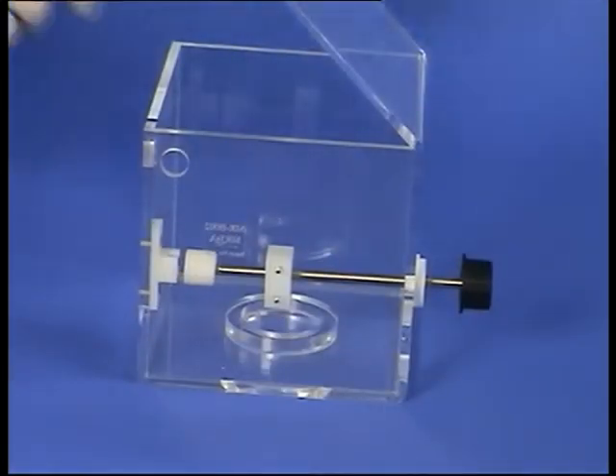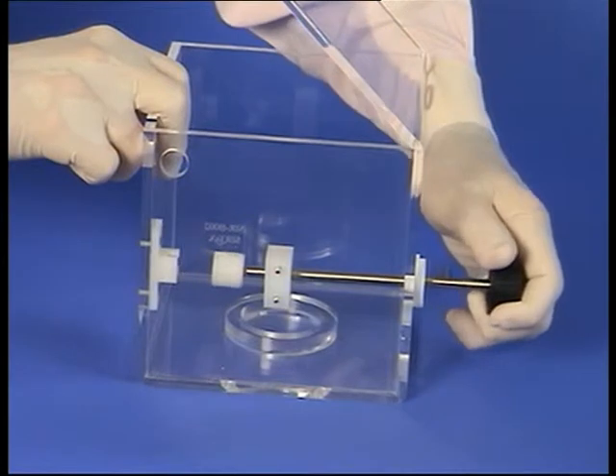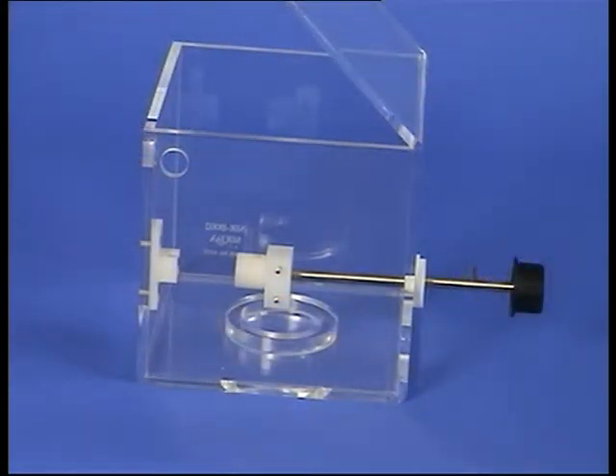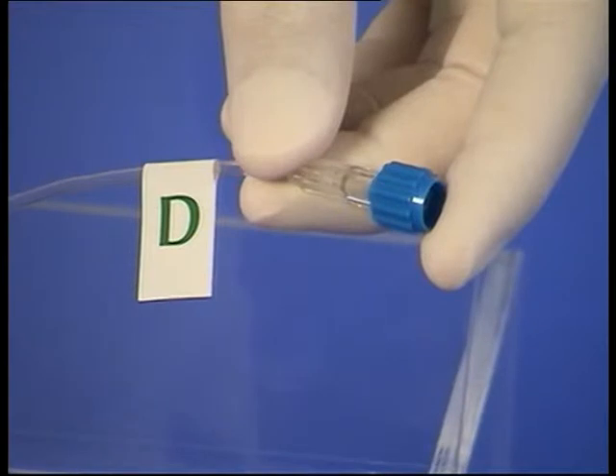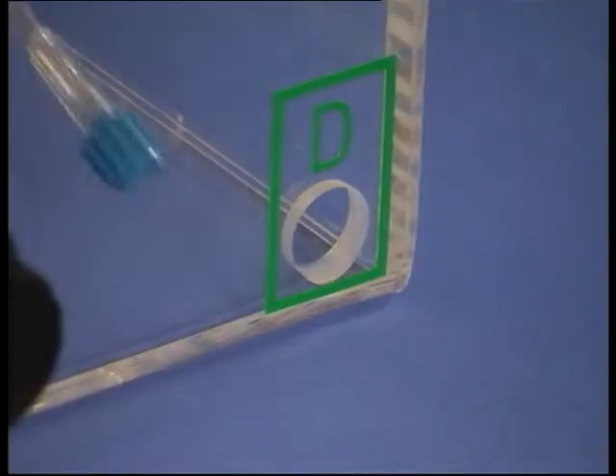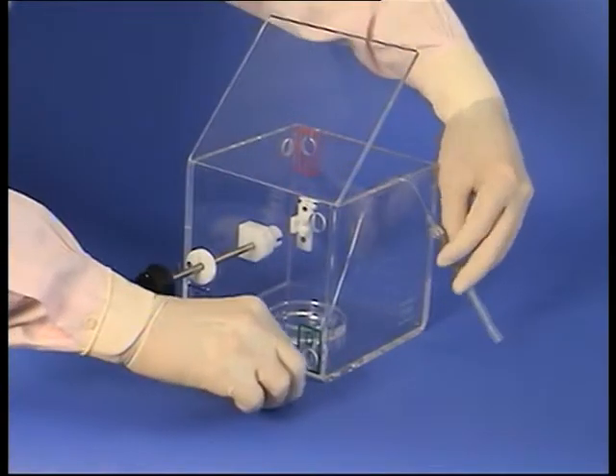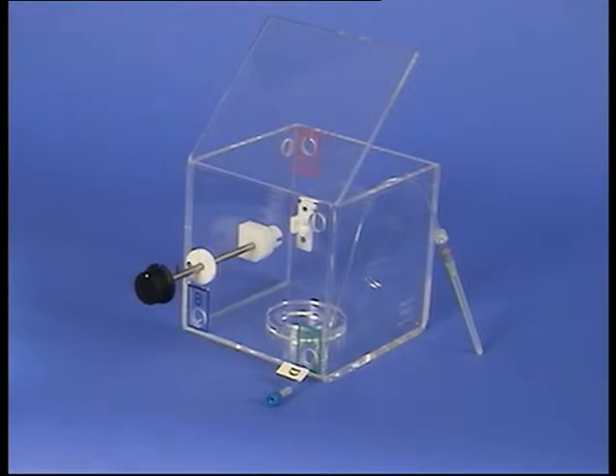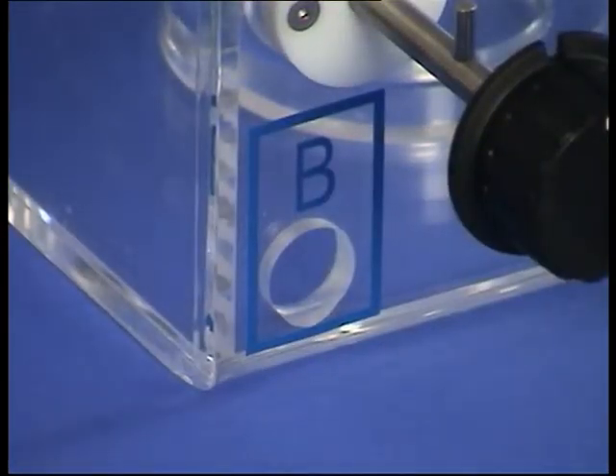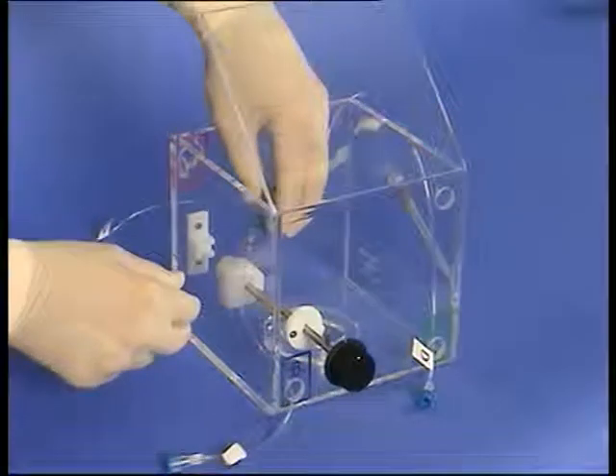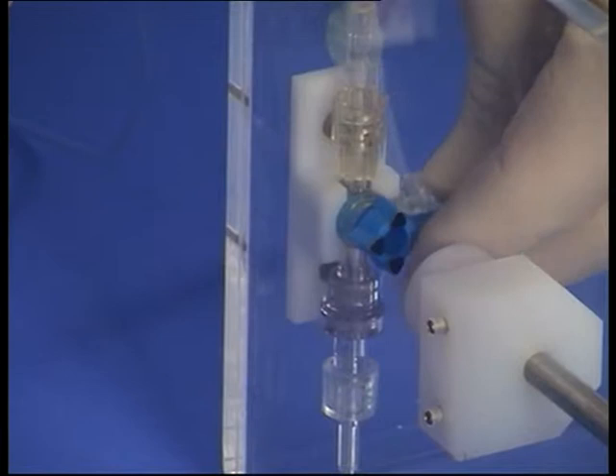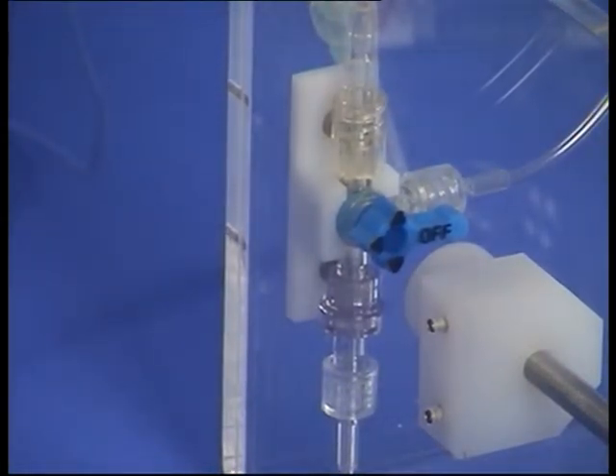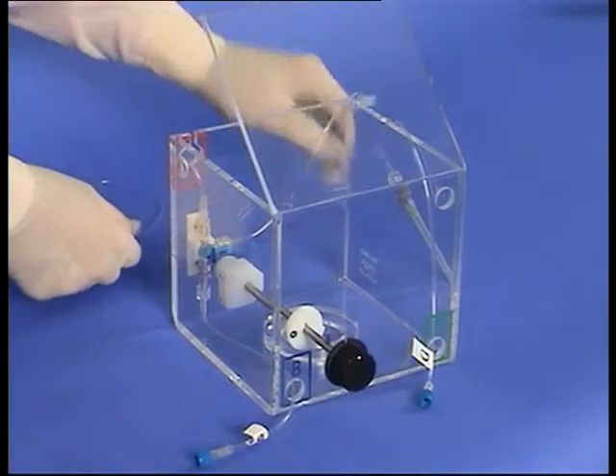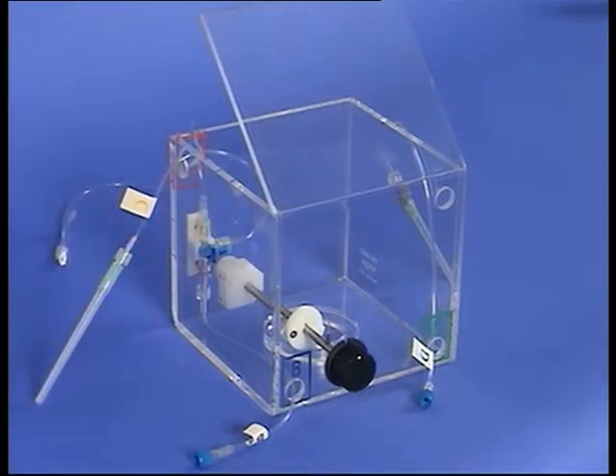To assemble the delivery set, start by making sure the control knob is pulled all the way back. Insert line D into the corresponding hole and drape the needle over the side of the box so that the needle is outside. For lines A, B, and C to be inserted, line B must be inserted first. Once B is in place, engage the 3-way stopcock in its holder at the back of the box. Line A can now be placed through its hole and line C draped over the side of the box.